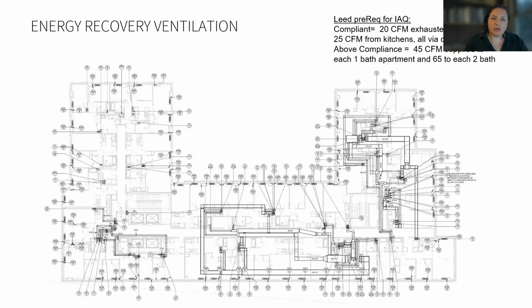But the GC was concerned with the additional cost of vertical shafts, so we conducted a cost comparison. Since the area under the horizontal ductwork inside apartments' habitable space would have been lower than 8 feet, it cannot be counted towards HBD compliant unit area, which is slightly larger than code minimum. So we had to include in the cost estimate raising each floor by 4 inches or 8 inches. In a central ventilation scenario, only the floors under the roofs need additional height to collect the ducts and bring them up to the units.